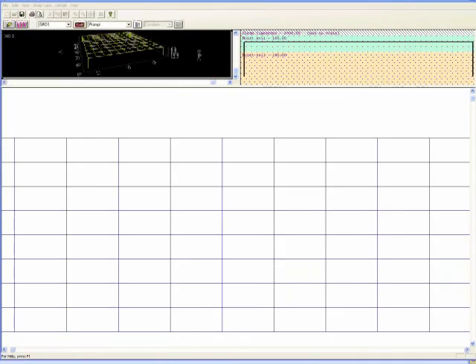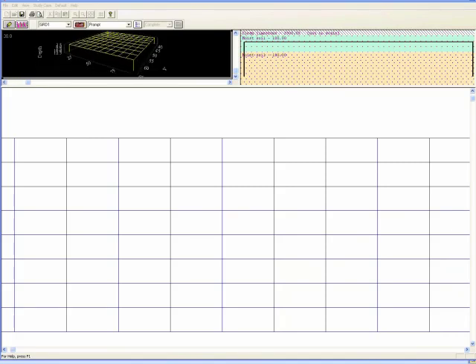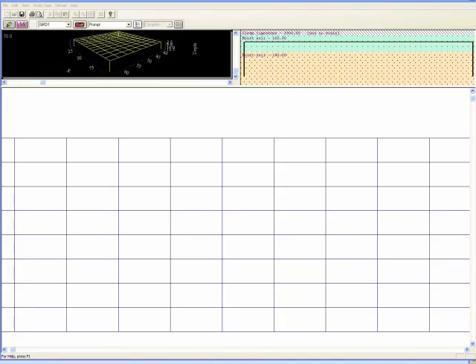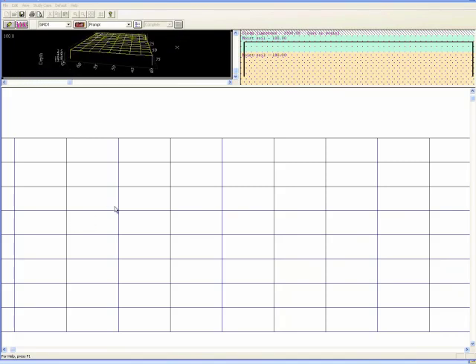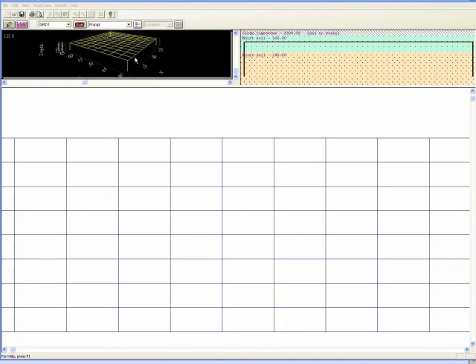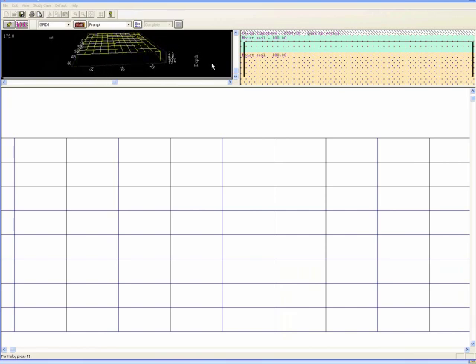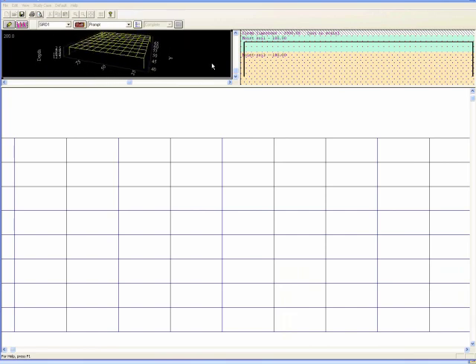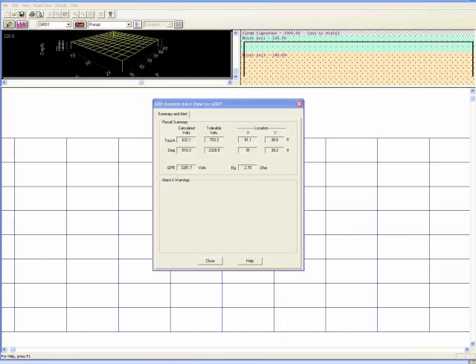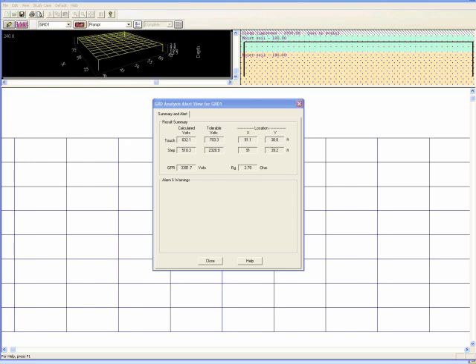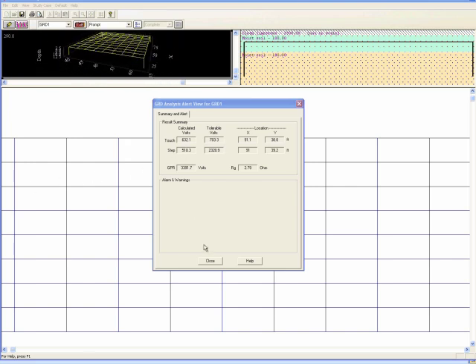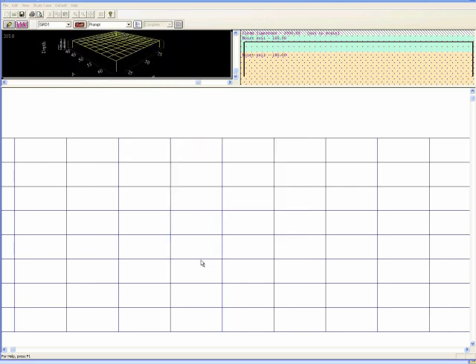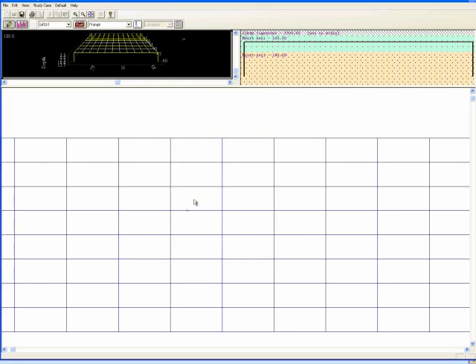Alternatively, the IEEE method could be used. However, according to the standard, the conductors and rods can only be added to the whole grid uniformly. In this case, an equivalent design with maximum voltage drop similar to FEM solution would require a total of 8 more conductors at both x and y directions.